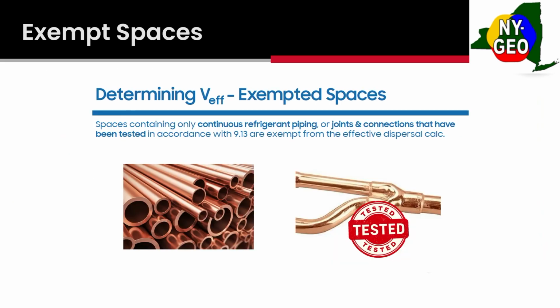So any continuous run of refrigerant piping or joints that have been tested in accordance with 9.13, essentially tested under pressure with no leaks, those are exempt from your spaces. So if we had refrigerant pipe coming down the middle of this conference room, we would not need to calculate this conference room in our EVDC.